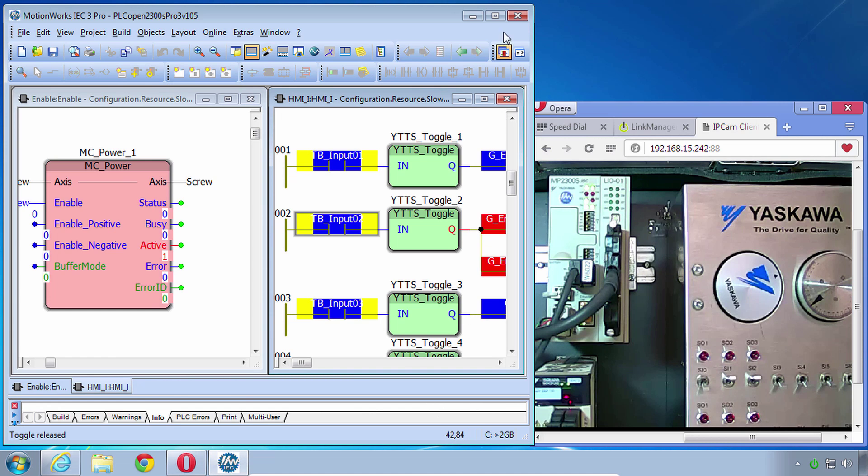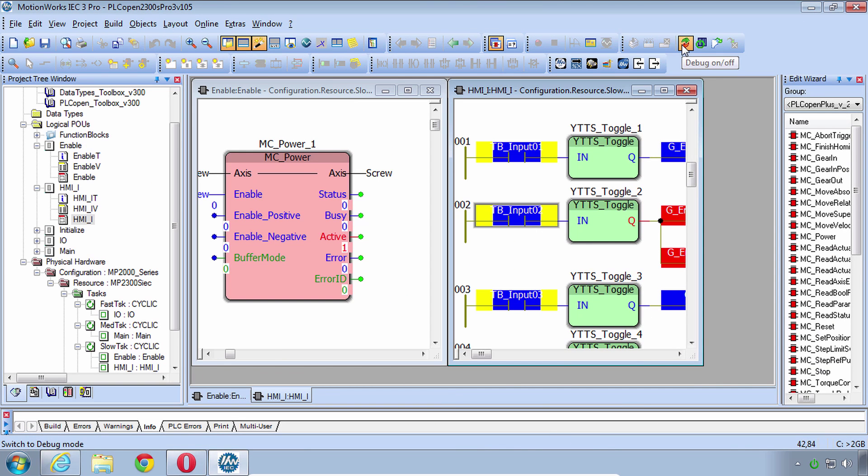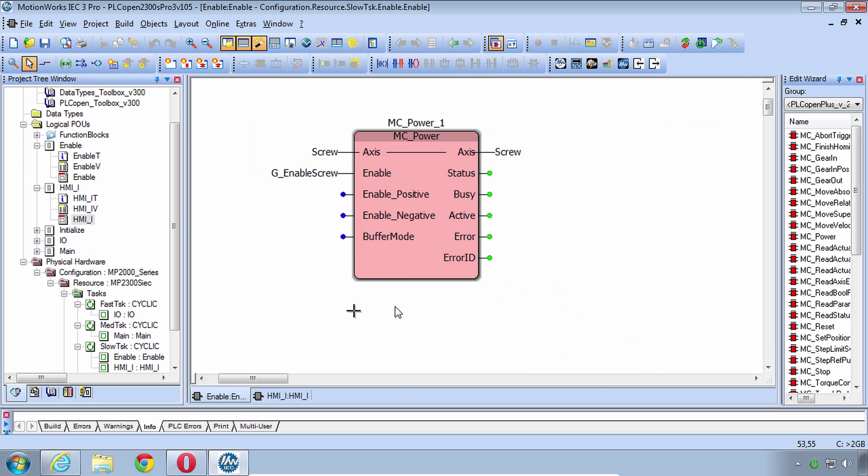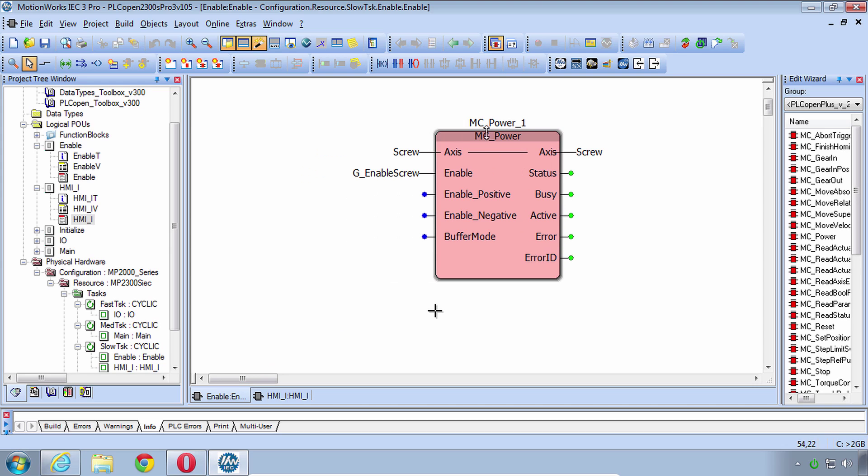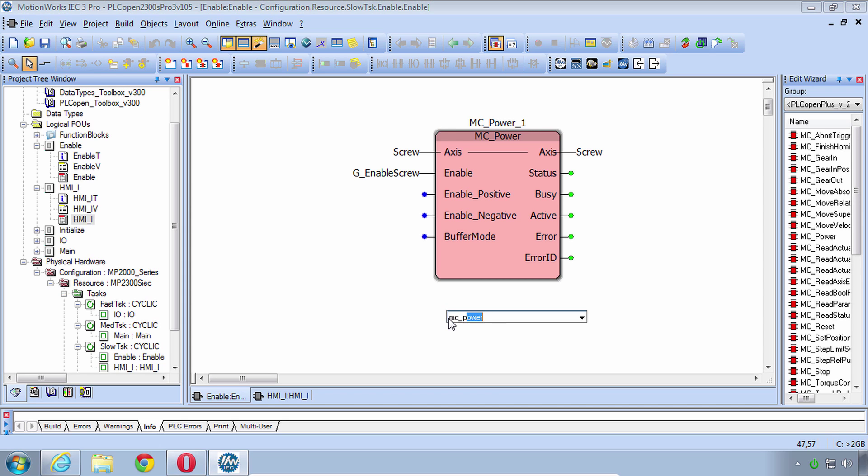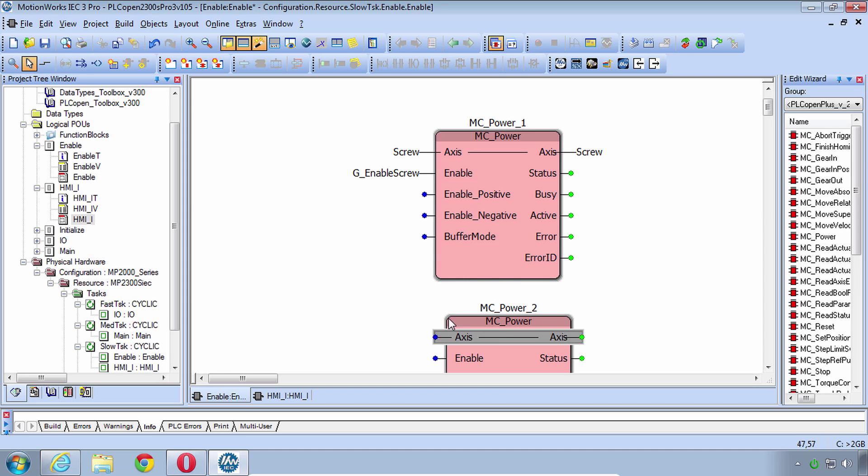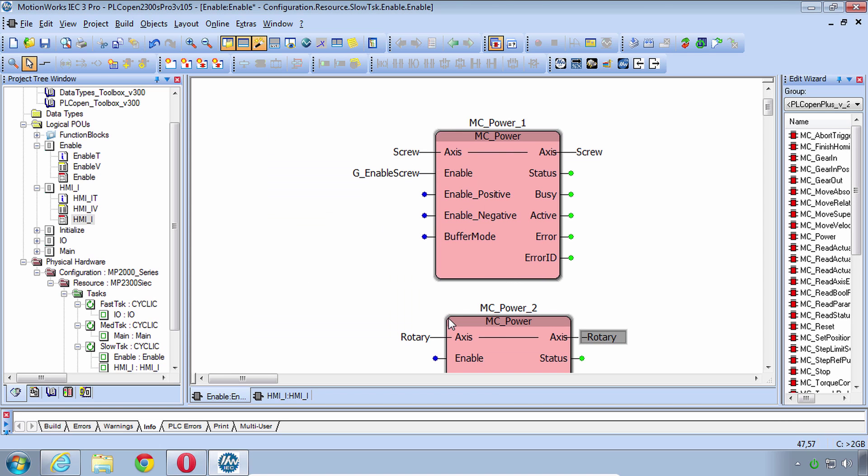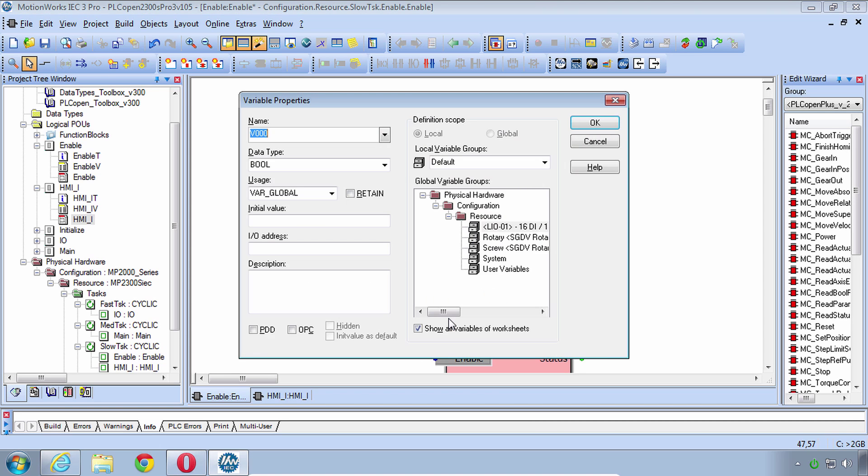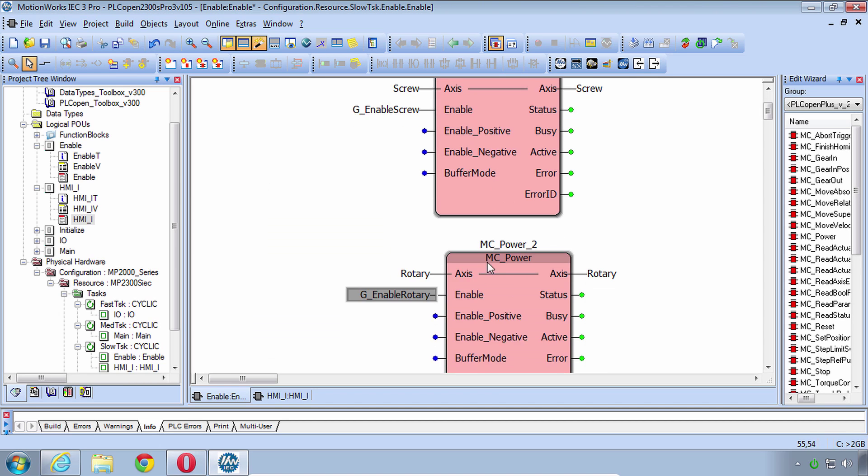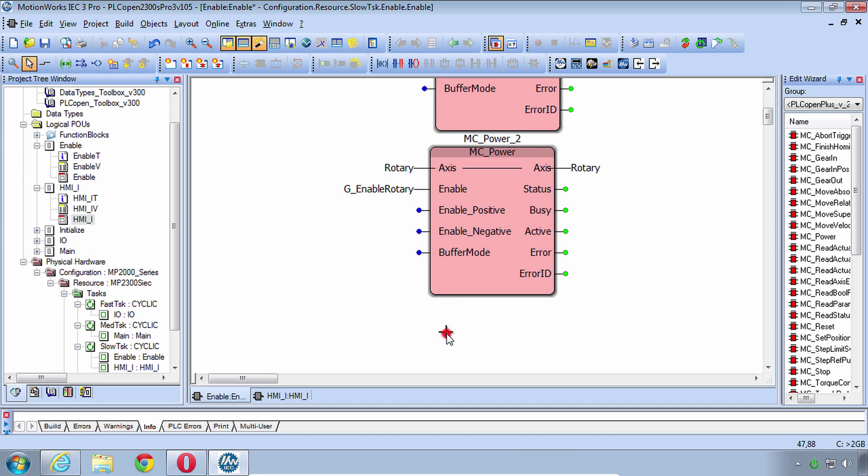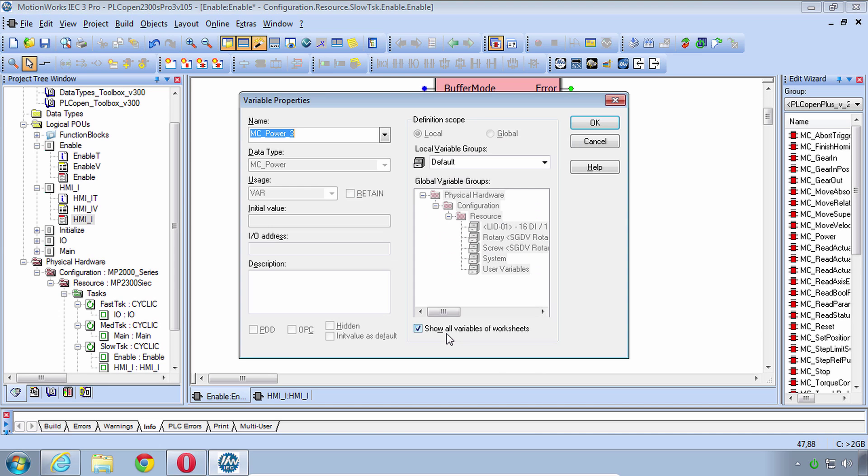OK I'm going to very quickly create servo enable for the other axes. Leave debug mode and Yaskawa's preferred method of programming is a vertical layout. We'll put the blocks going down because we'll often have ladder rungs out to the left or out to the right or maybe timers or other logic so we tend to do more of a vertical block layout. One shortcut is to simply type the name of the block like I'm doing here. You can use the Enter key to save some time here so we've got rotary, enter, use the arrow keys to go over to enable. We've got G enable rotary, line that one up. Come down here another MC power number 3 that will be virtual.